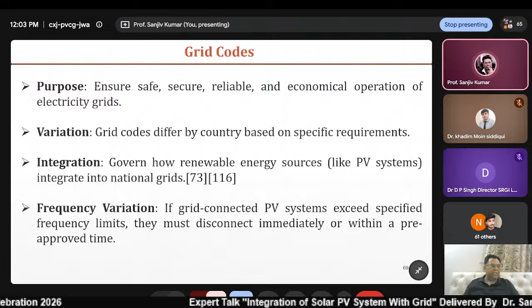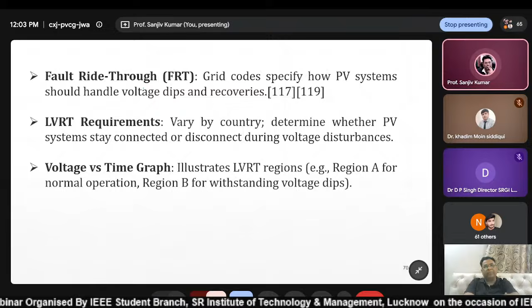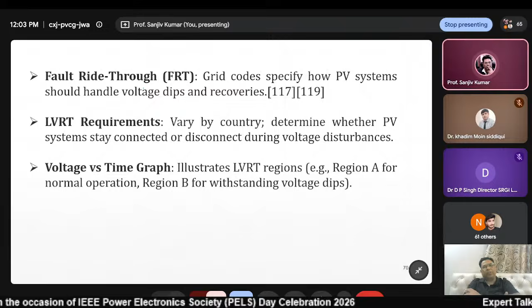How much load it can handle, or how much fault ride through capacity means, if some fault occurs because of your PV cell and all, then how much voltage dip is allowed? Suppose it is 240 and for 2 or 3 cycles it goes to 200 - is it acceptable? Yes, if it is acceptable, then it goes through. Otherwise, the system has to be tripped. That is called fault ride through capacity that we have to take care of.